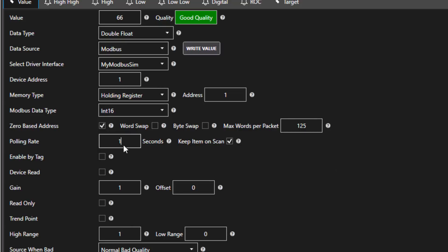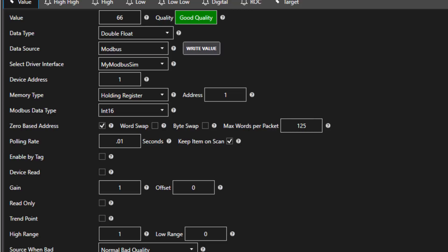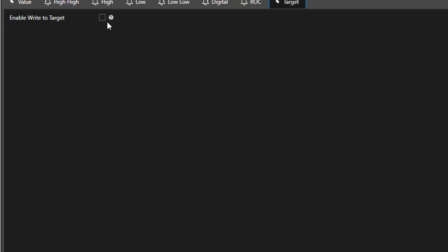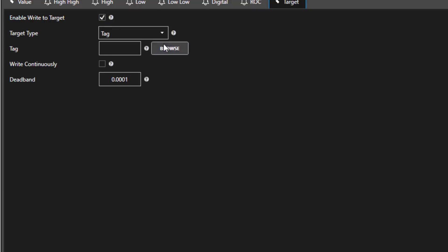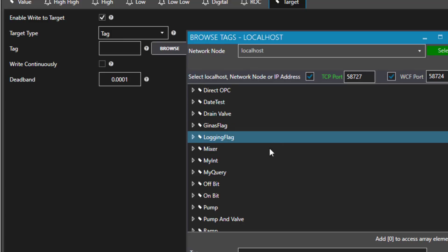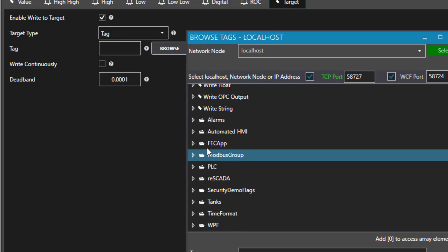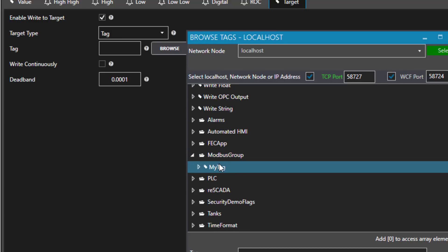Let's speed things up a bit and show some data route functionality. I am going to set the polling rate now to 10 milliseconds and we can view the packets going in and out of the simulator. Next, I will take another data source, this ramp tag, and I am going to change the simulation rate of that also to 10 milliseconds. Then I will go to the target tab and I will check here to enable write to target. I will then browse to the my tag tag that I created under the Modbus Group group and select it.